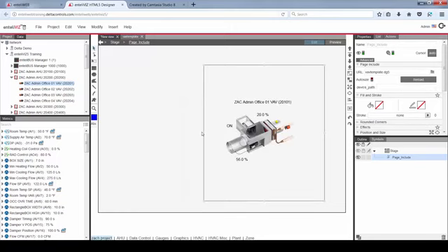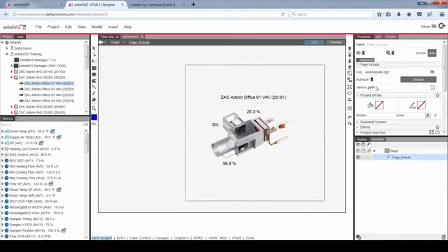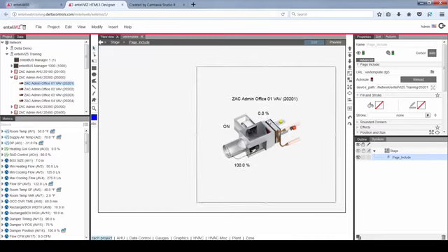You can see my VAV template now shows up. And look what's here as well: I've got that device path property that I created. And if I just drag in a device reference, 20101, 20102, 20103, they all work nicely. So you really want to get in the habit of checking your relativization before you get too far.